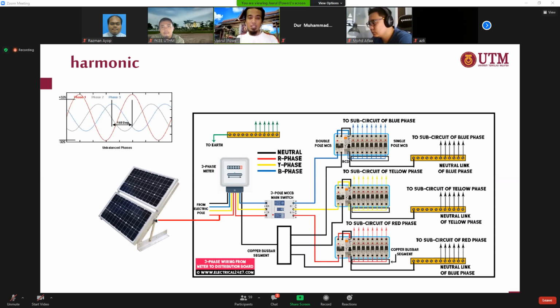So it is recommended that if you are using a three-phase supply for your house, make sure that you are using a three-phase inverter as well, so that the power being injected by the PV will be equally distributed across each phase. Try to avoid having a three-phase system and three-phase meter in your house, even though it is actually a single-phase load, and then connecting a single-phase PV. If you use this condition, it will make the voltage imbalance worse.